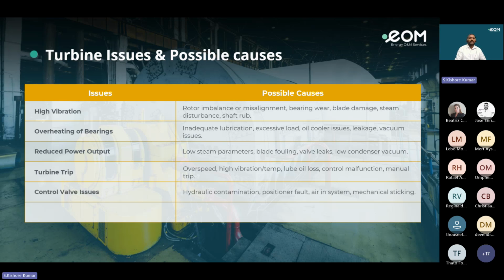Control valve issues: I already said a couple of times that hydraulic oil contamination causes the hydraulic system or the governor system to start giving faults and not operate properly. It will get stuck and sometimes may not operate. That is a major cause of control valve issues. I recommend always checking the oil and doing the analysis, and if the oil is too bad, replace it with new oil, in order to safeguard your turbine and your governing control systems and their precise parts.